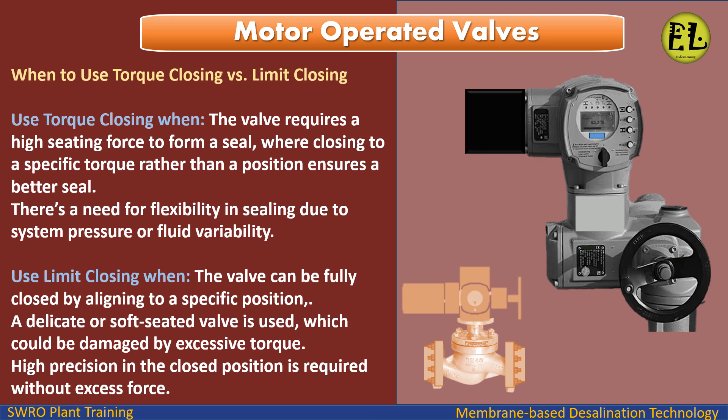When to use torque closing versus limit closing: Use torque closing when the valve requires a high seating force to form a seal, where closing to a specific torque rather than a position ensures a better seal, or where there is a need for flexibility in sealing due to system pressure or fluid variability. Use limit closing when the valve can be fully closed by aligning to a specific position, or a delicate or soft-seated valve is used which could be damaged by excessive torque, requiring high precision closing.